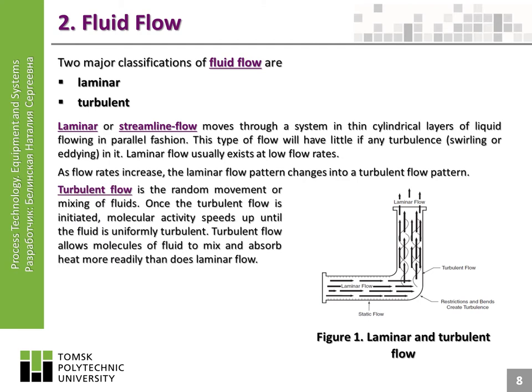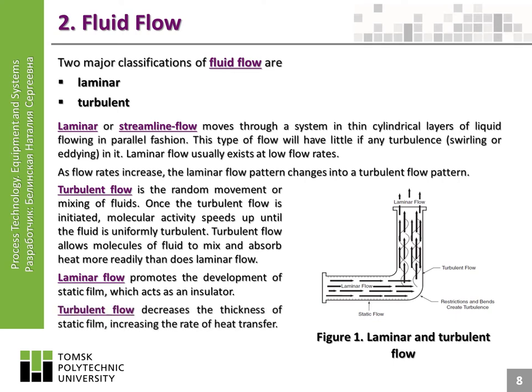Turbulent flow is the random movement or mixing of fluids. Once turbulent flow is initiated, molecular activity speeds up until the fluid is uniformly turbulent. Turbulent flow allows molecules of fluid to mix and absorb heat more readily than does laminar flow. Laminar flow promotes the development of static film, which acts as an insulator. Turbulent flow decreases the thickness of static film, increasing the rate of heat transfer.